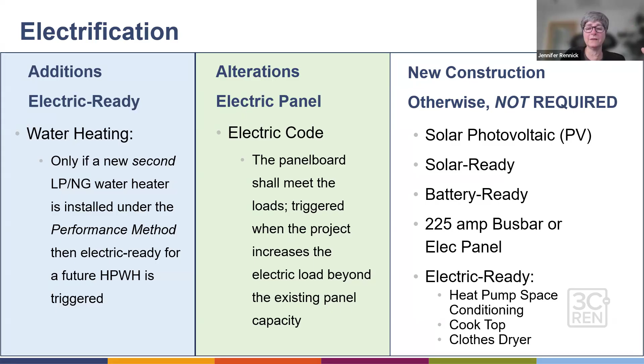Otherwise, this part of electric ready isn't required. So I put this in here for reference. We haven't seen it come up very much, but it might. The other reason I put it in here is because the question comes up all the time, like how much space do I need for a heat pump water heater? And I found that the 30 by 30 by 7 feet that you have for the heat pump water heater ready is actually a good rule of thumb to use for the space you need for your heat pump water heater that you're going to install.